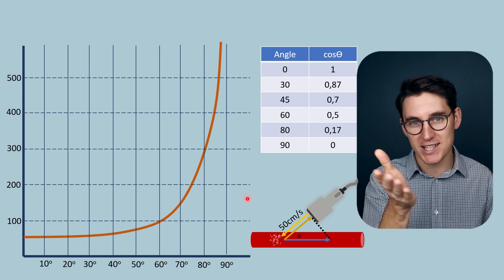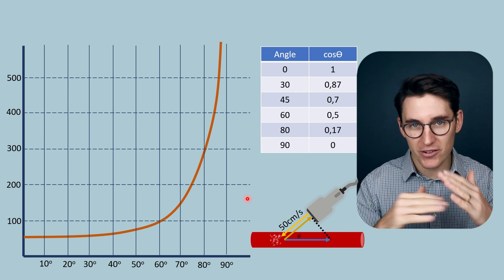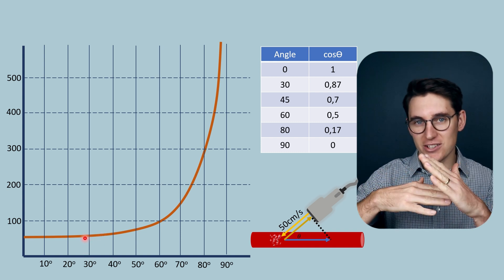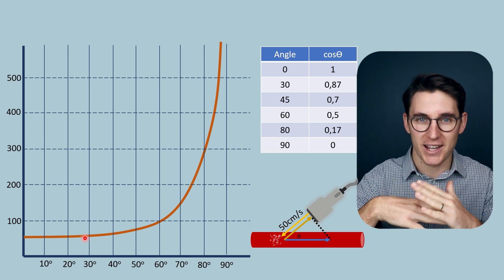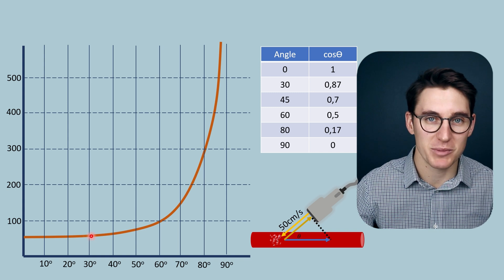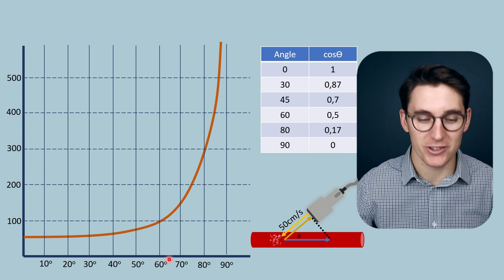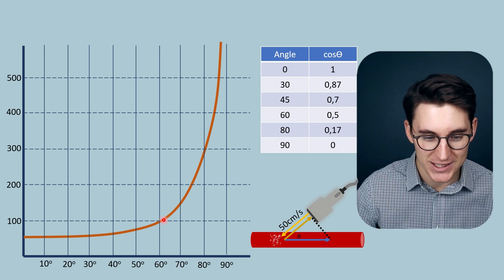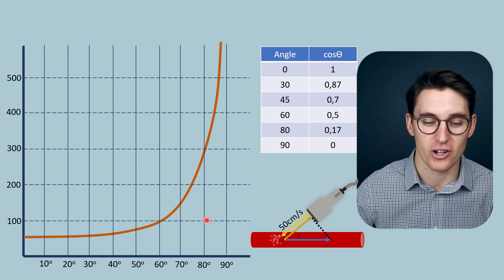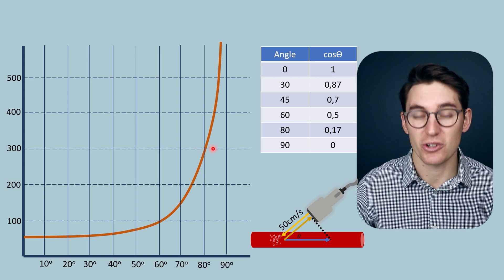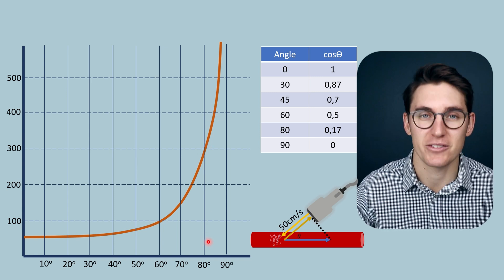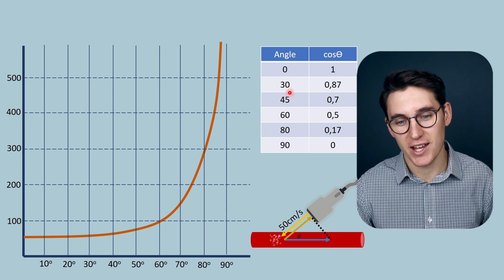The issue arises when setting our ultrasound machine's angle — we'll never have it perfectly accurate. If we're using a 30 degree angle and we're off by 5 degrees, the calculated value at 30 degrees versus the actual at 35 degrees is very similar — perhaps 55 versus 60 cm/s. As this angle increases and we're off by 5 degrees, the actual and calculated values start becoming very different. Above 60 degrees there's a real exponential curve, and at 80 degrees a 5 degree error results in a calculated velocity over 100 cm/s faster than the actual value.